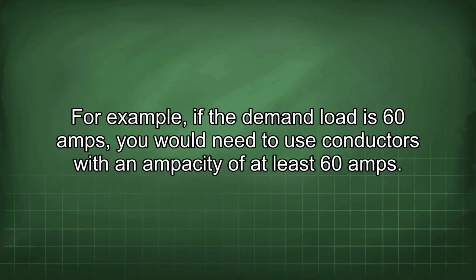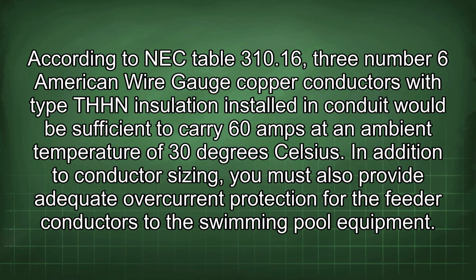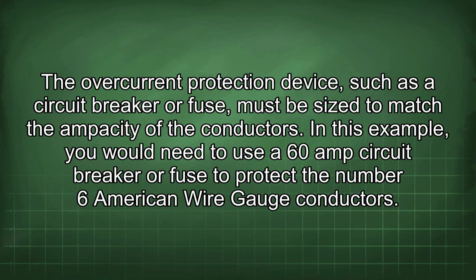For example, if the demand load is 60 amps, you would need to use conductors with an ampacity of at least 60 amps. According to NEC Table 310.16, 3 number 6 American wire gauge copper conductors with type THHN insulation installed in conduit would be sufficient to carry 60 amps at an ambient temperature of 30 degrees Celsius. In addition to conductor sizing, you must also provide adequate overcurrent protection for the feeder conductors to the swimming pool equipment. The overcurrent protection device, such as a circuit breaker or fuse, must be sized to match the ampacity of the conductors. In this example, you would need to use a 60 amp circuit breaker or fuse to protect the number 6 American wire gauge conductors.